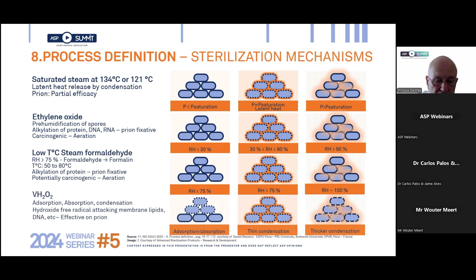For all sterilization modalities, vacuum at various levels is needed to eliminate gases that could prevent condensation, which, as you saw, is fundamental for all sterilization processes, although in a different manner. For all chemical processes, ethylene oxide, LTSF, and H2O2, efficacy varies according to temperature and mainly according to the concentration of the sterilizing agent. And to summarize, can you go to the next slide now?